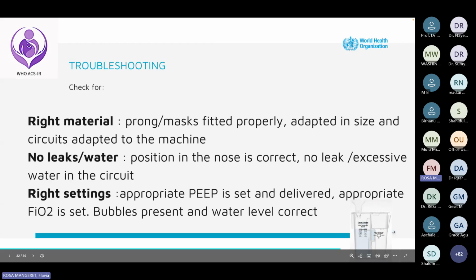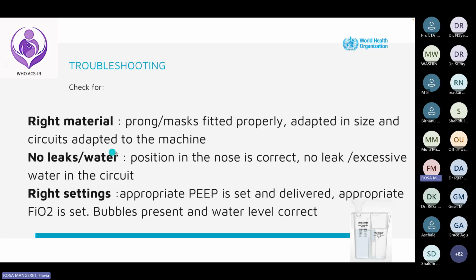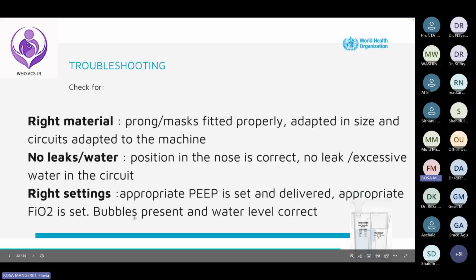So troubleshooting, basically: right material, no leaks and no water, and right settings. If CPAP's not working, check that prongs and masks are fitted properly, adapted in size and adapted to the machine. There are no leaks, no water. The position in the nose is correct. There is no leak or excessive water in the circuit. And the right settings, that you have the appropriate PEEP and the appropriate FiO2. Also something important for bubble CPAP, that you have bubbles present and the water level is correct. As you see in this image here, when you fill the water, it has to overflow a little bit. This is for the Fisher and Paykel. For the other machines, it might be different, but always make sure that the level is correct, so you have the right pressure delivered.